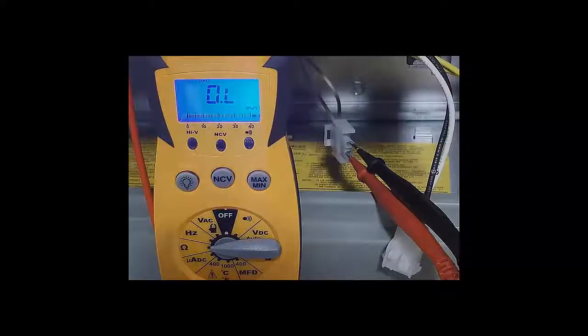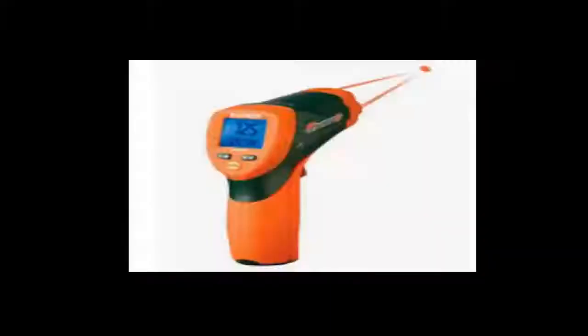Also, I have seen on very few rare occasions in my 40 plus years of doing this, an igniter that had correct power, ohmed out okay, and was glowing red, but the gas wouldn't ignite. In order to figure this one out, I had to use an infrared thermometer to check the surface temperature of the igniter while it was glowing. And what I found was, for whatever reason, they were not getting hot enough. If igniters don't reach 1200 degrees, natural gas won't ignite. And for propane, the igniter must get to at least 900 degrees.